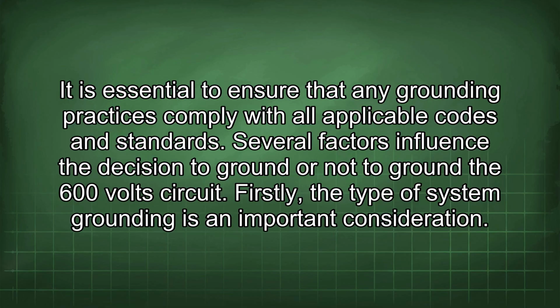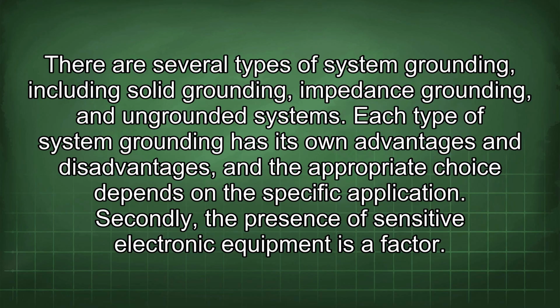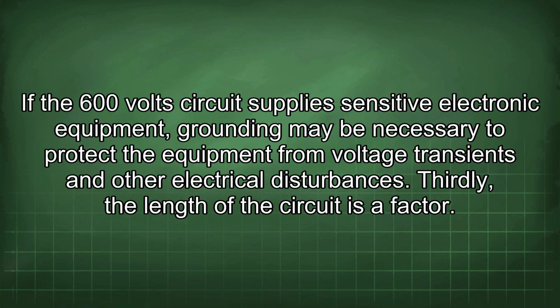Several factors influence the decision to ground or not to ground the 600 volt circuit. Firstly, the type of system grounding is an important consideration. There are several types of system grounding, including solid grounding, impedance grounding, and ungrounded systems. Each type of system grounding has its own advantages and disadvantages, and the appropriate choice depends on the specific application. Secondly, the presence of sensitive electronic equipment is a factor. If the 600 volt circuit supplies sensitive electronic equipment, grounding may be necessary to protect the equipment from voltage transients and other electrical disturbances. Thirdly, the length of the circuit is a factor.